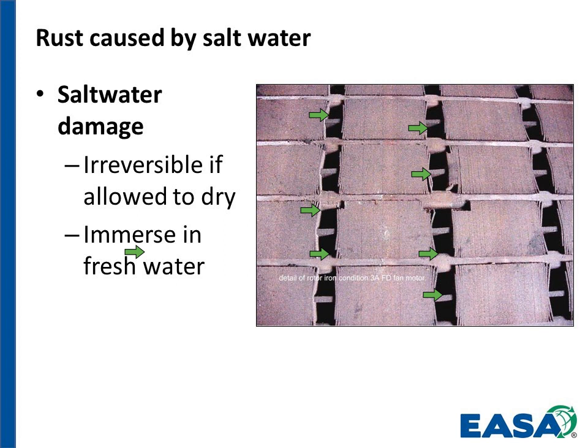So we need to recognize that the motors we're repairing, if they've been immersed in salt water and allowed to dry, are going to need to be replaced. We may be looking at a 5 to 10 year remaining service life, if that. So if we can get motors in and immerse them in fresh water, if you have a lake close by, a large swimming pool, heavy dumpsters, any sort of holding tank that's not being used for something else, we can clean the electric motors and generators and immerse those in water.